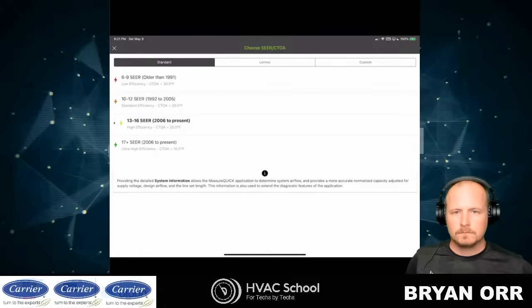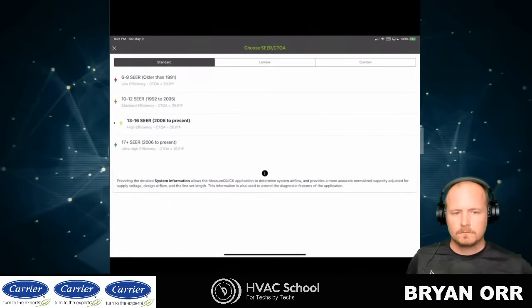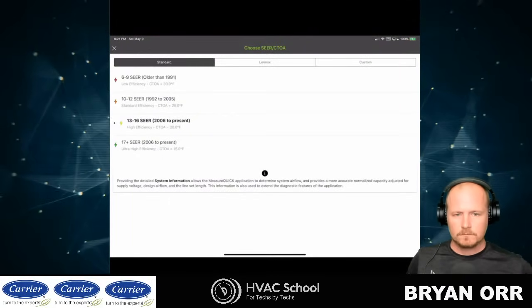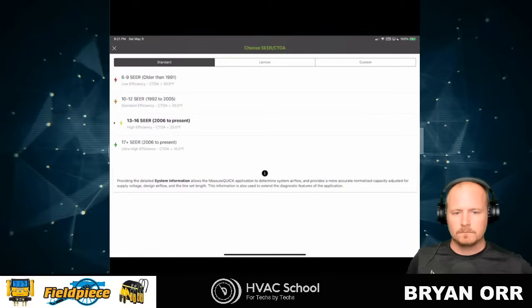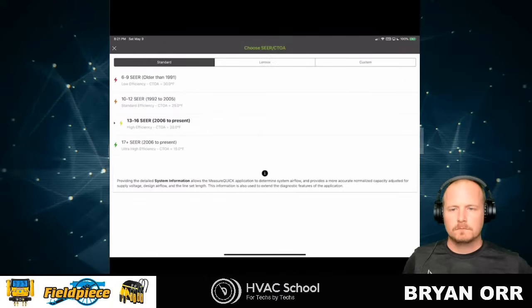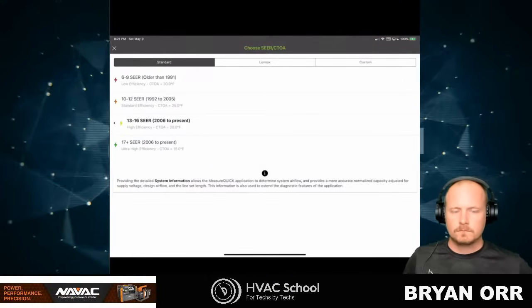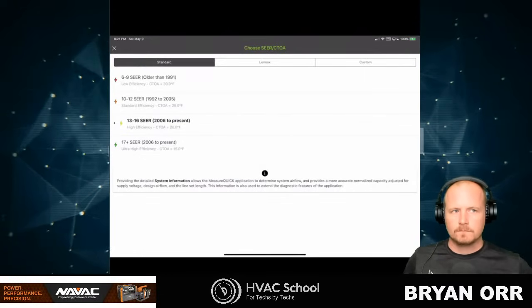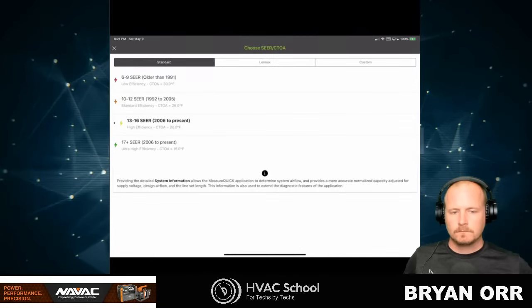When you go out there, there's what we call acceptable ranges of operation, and it's really hard. First everybody tells you, oh well, just take it up to 118 and 350 and you'll be fine. And okay, that works for one set of conditions, but what about the other 10,000 sets of conditions that we run under?